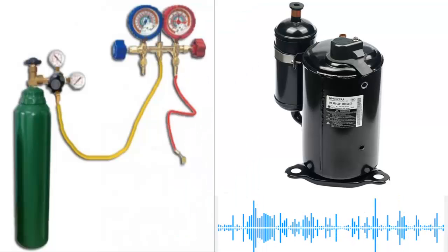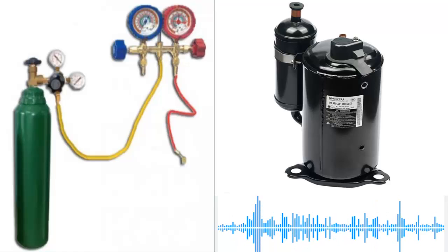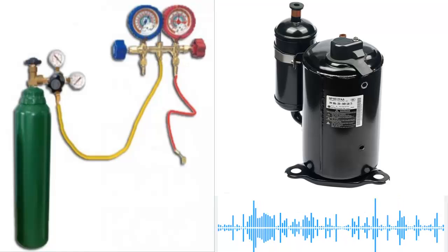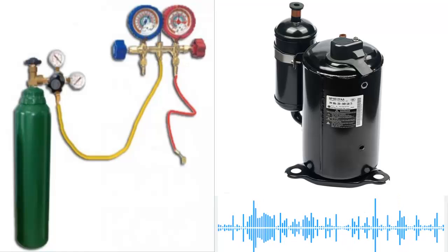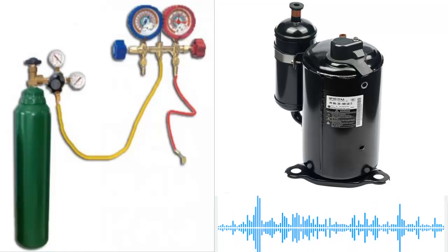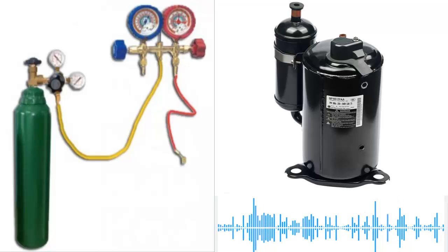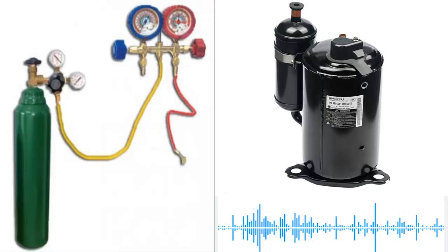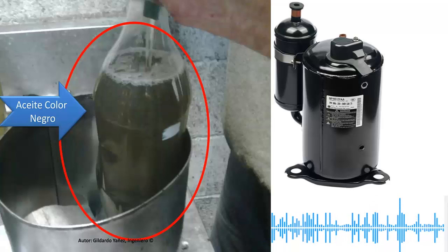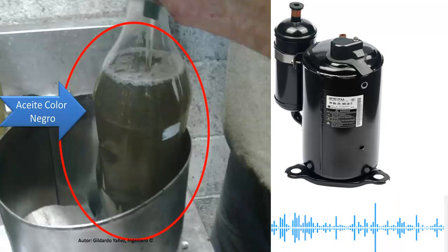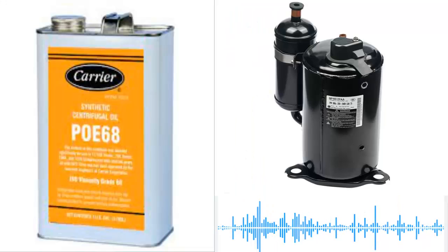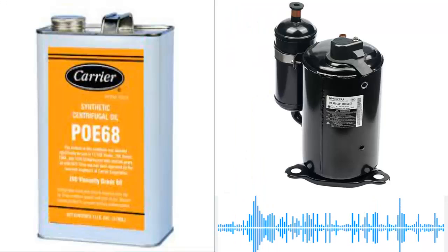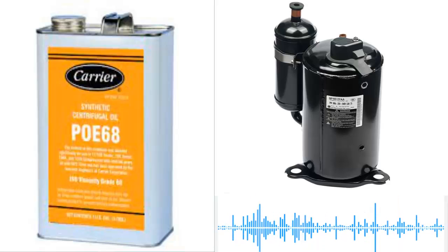6. Oil Replacement. After cleaning, replace the oil with new and high quality oil. Make sure that the oil used is suitable for your air conditioning system. The most common practice to determine the amount of oil to replace is to use the amount of old oil in the compressor as a reference, and always add a larger amount — on average, an additional 30%. However, if you have the oil measurement recommended by the compressor manufacturer, it is better to provide the exact measurement.